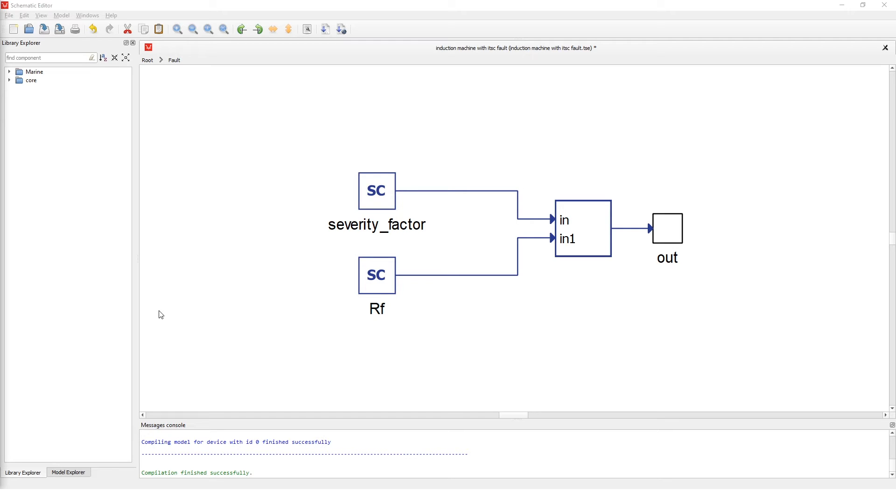Zero means that the path of the short circuit starts and ends at the same end of the winding, while for non-zero values the second point of the short circuit moves towards the other end of the winding, where one means that the whole winding is shorted.